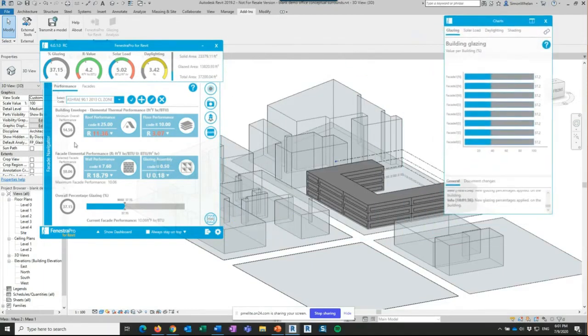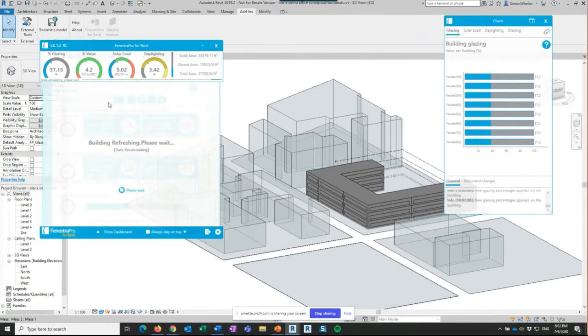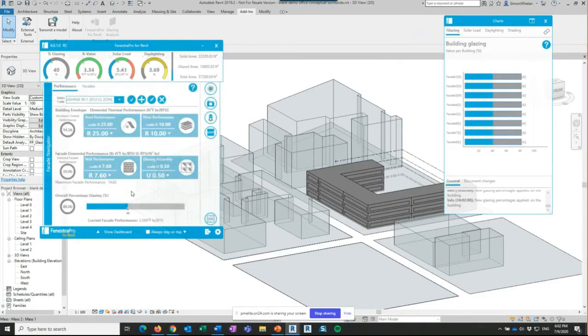But I think we said, and you guys will know this better than me, that ASHRAE 90.1 may have a max wall to window ratio of 40%. So we can apply that 40%, and that will update, changing that 37.2% to 40%. And as I said, we can start getting an understanding of not huge heat gains to different orientations, and daylighting, and we're going to have some shading on different orientations, et cetera, et cetera.